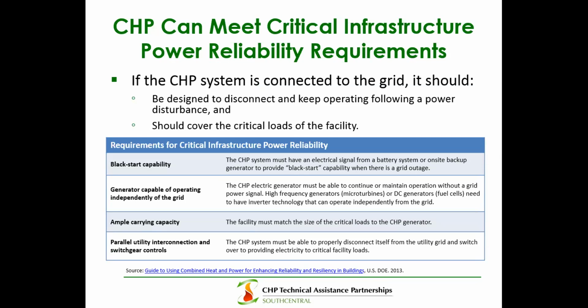So there are some key components that have to be considered. It has to have black start capability, so it can start and get going once the grid goes down, and operate independently of the grid. It needs ample carrying capacity, so it can operate more than just exit signs or some lights in the building; you want it to be able to carry vital services within that building.